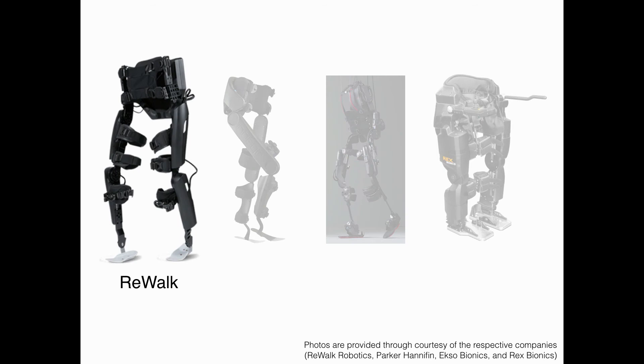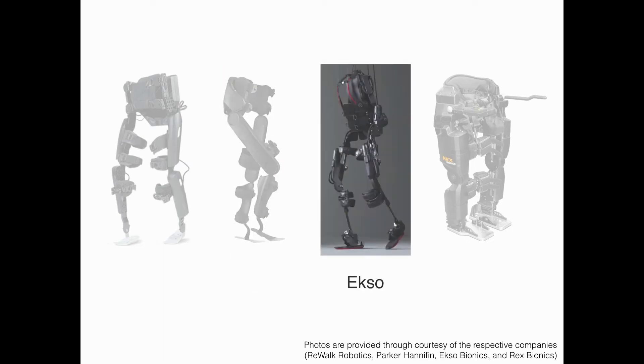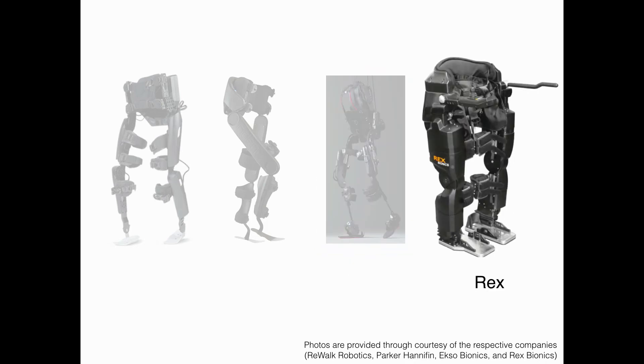ReWalk is the first exoskeleton cleared in the United States by the FDA. Its de novo application was approved in 2014, and it has been used as a predicate device for other devices that claim to be substantially equivalent. Indego's 510K application was approved by the FDA in 2016. Ekso was also cleared to market in 2016. We also reviewed Rex from Rex Bionics, which is a self-supporting device with automated movements such as forward, backward, turn, and also stand and sit.